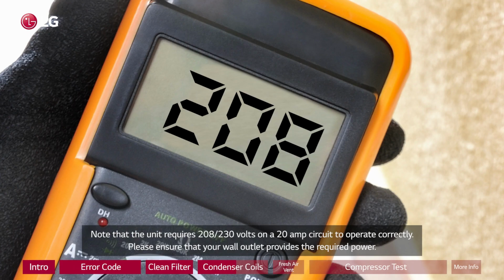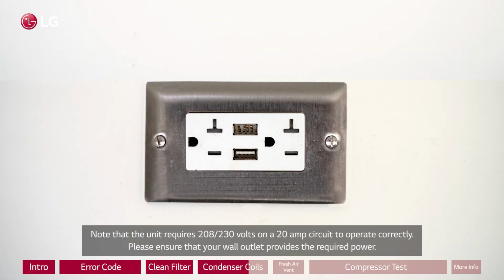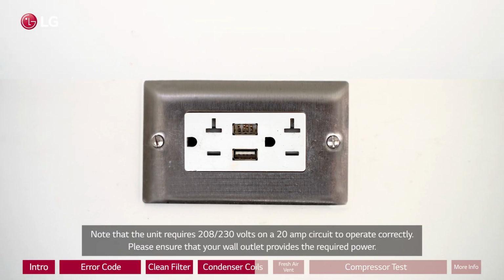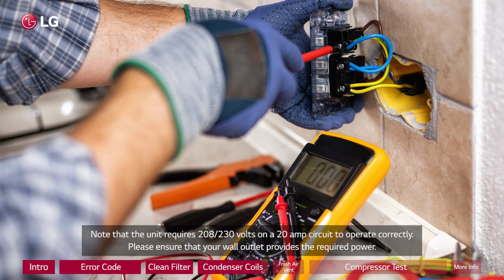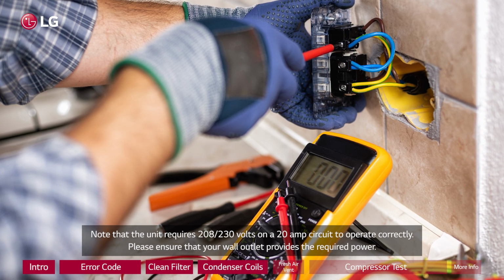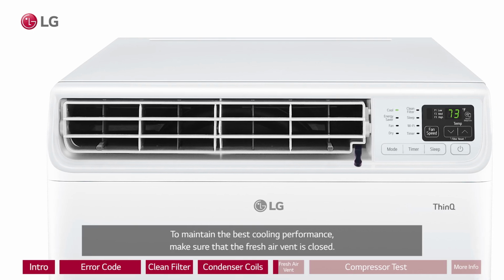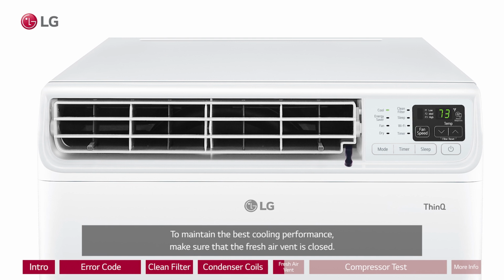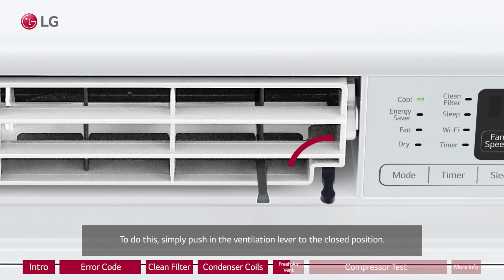Note that the unit requires 208/230 volts on a 20 amp circuit to operate correctly. Please ensure that your wall outlet provides the required power. To maintain the best cooling performance, make sure that the fresh air vent is closed. To do this, simply push in the ventilation lever to the closed position.